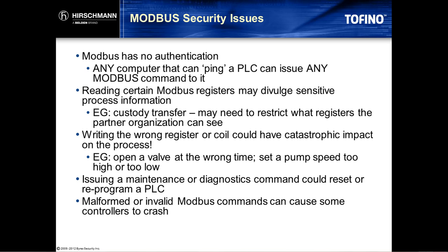Finally, some of these Modbus capable devices have some errors in their implementation of the Modbus command set. Specifically, we found some devices that don't do a good job of error checking on commands that are sent to them. And as a matter of fact, the Tofino SCADA security simulator includes an example of one such vulnerability which can cause the PLC to crash.